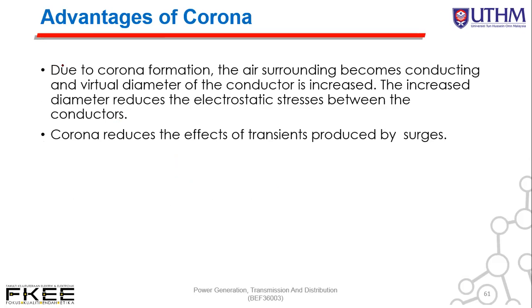Ada kelebihan corona. Due to corona formation, the air surrounding become conducting and virtual diameter of conductor is increased. Okay, let's say this is conductor and this is corona. So look like that the diameter of conductor is increased. The increased diameter reduces the electrostatic stress between the conductor. Also, corona reduces the effect of transient produced by surge.